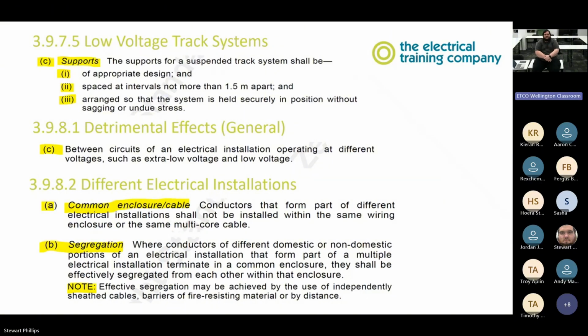Cool. Segregation. So when conductors of different domestic or non-domestic portions of an electrical installation that form part of a multiple electrical installation terminate in a common enclosure, they shall be effectively segregated from each other within that enclosure. Probably every 3 or 4 meters. I just wrote on the conduit with a Sharpie, like a very good permanent marker. Cool. Note: effective segregation may be achieved by the use of independently sheathed cables, barriers of fire-resisting material, or by distance. So that's how I achieved my segregation: barriers with conduit.